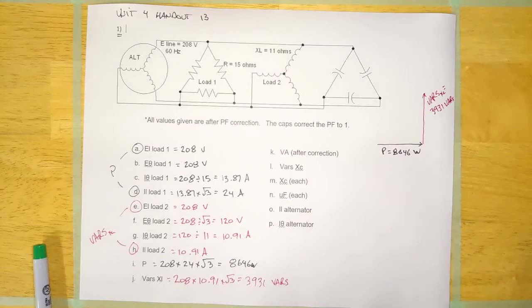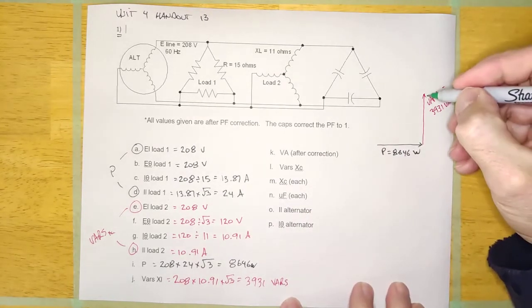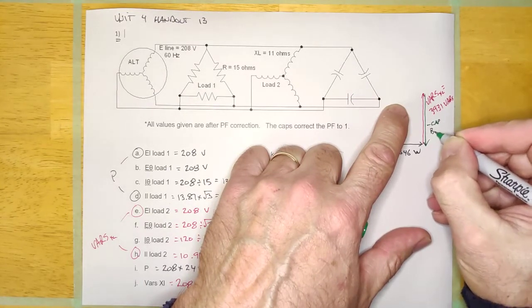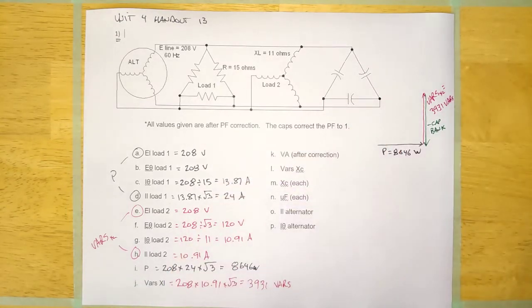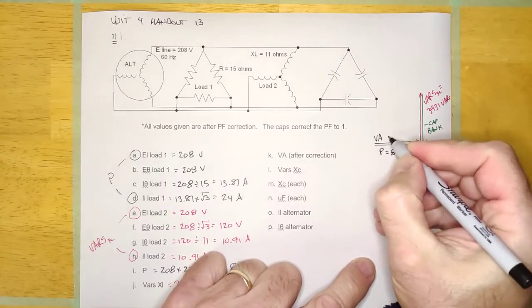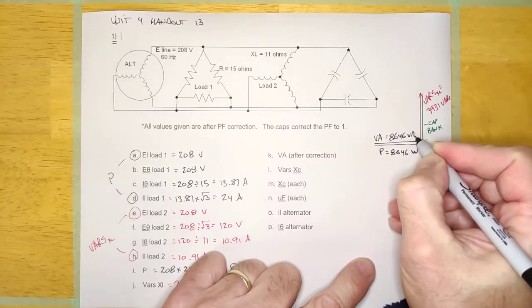Since we're correcting to unity, that capacitor bank is going to take care of all of the reactive power. Your VA, once corrected to unity, is going to be equal to the watts: 8,646 volt-amps.